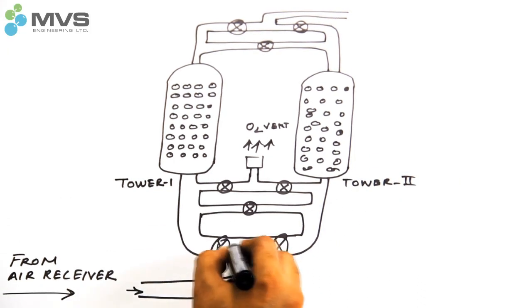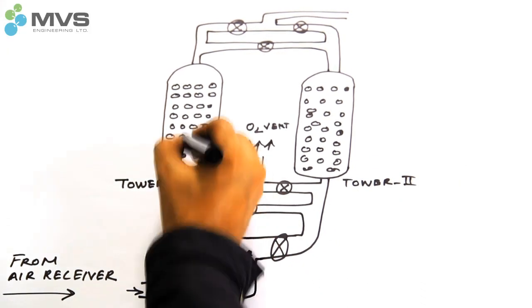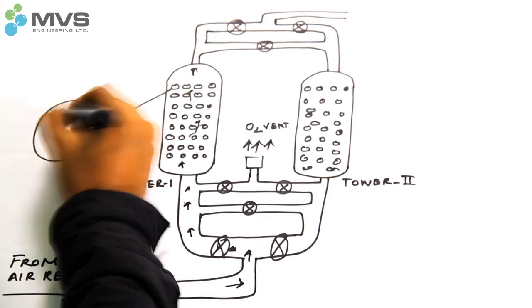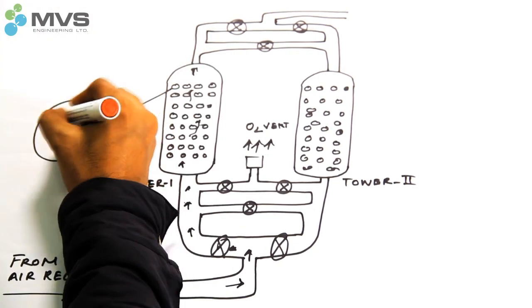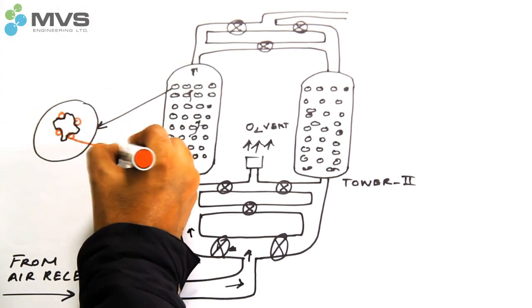PSA technology comprises two molecular sieve-filled towers. Compressed air is passed through tower 1. This compressed air pressurizes the tower. Oxygen molecules are smaller in size and get trapped within the pores of the molecular sieves.